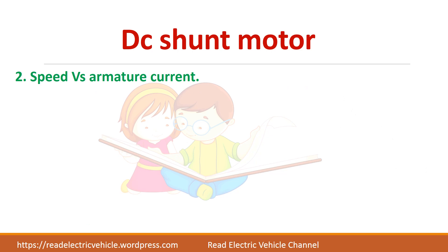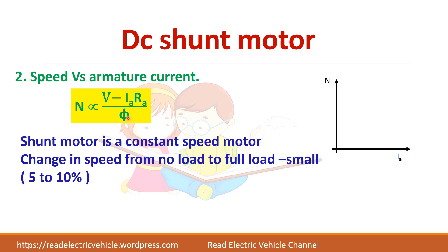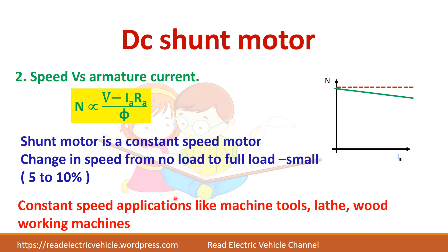Next, the speed versus armature current characteristic. Speed is directly proportional to back EMF divided by flux. Since flux is almost constant in a shunt motor, as the load increases there is only a small drop in speed from no-load speed. It acts almost as a constant speed motor and is preferred for constant speed applications like machine tools, lathes, and woodworking machines.